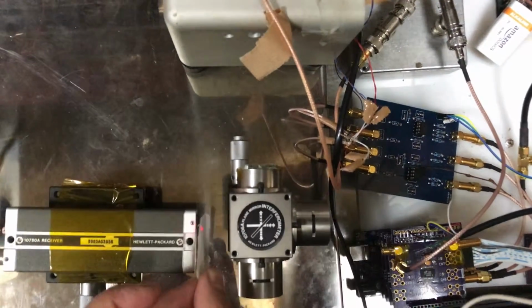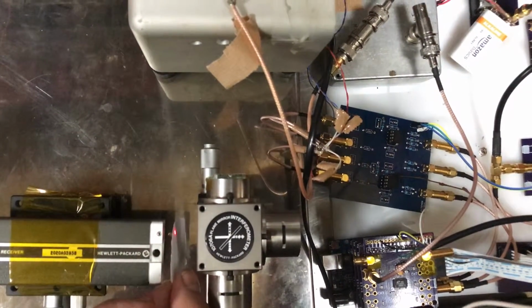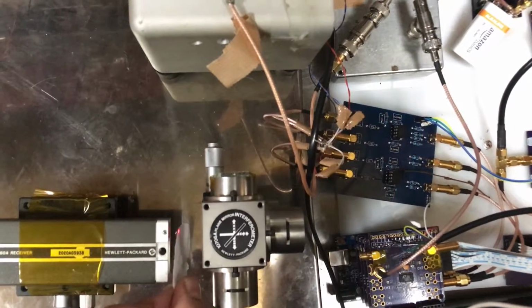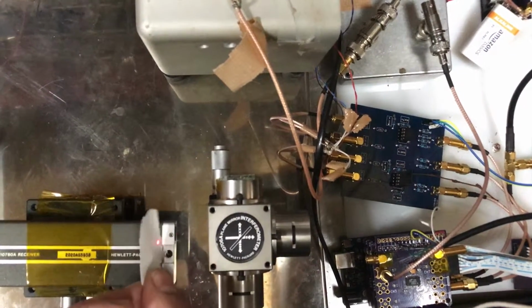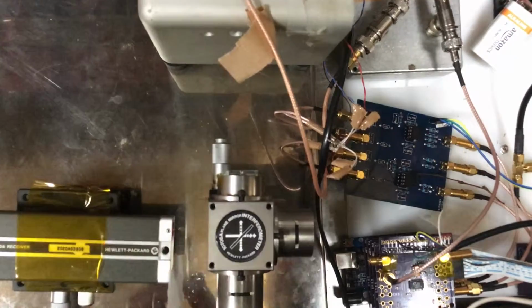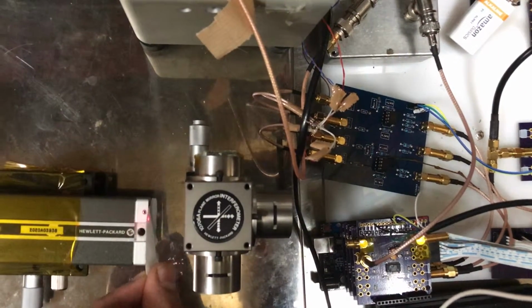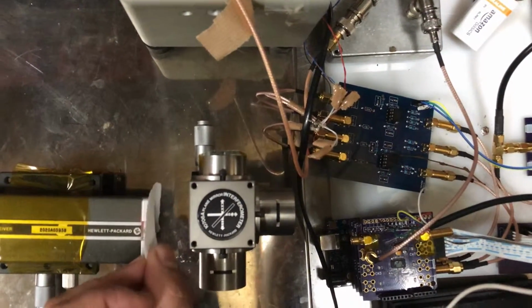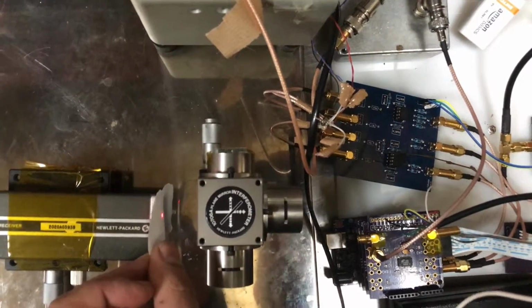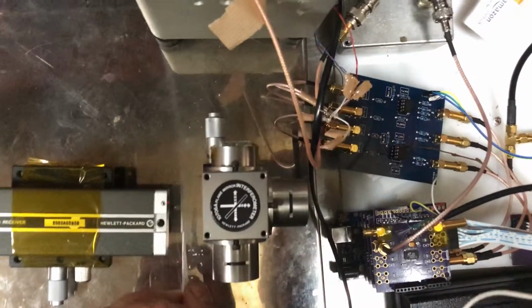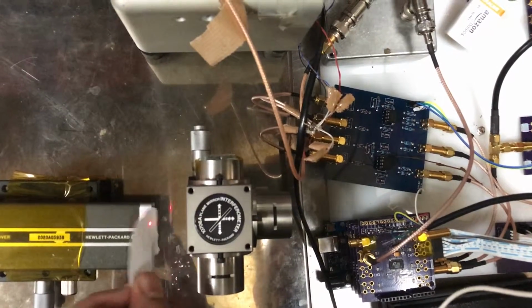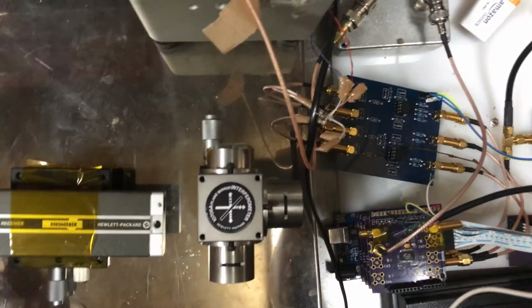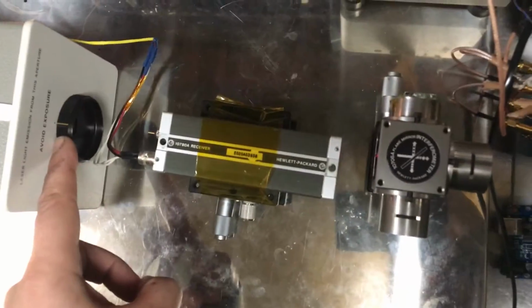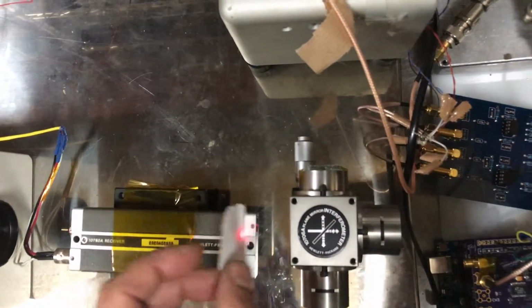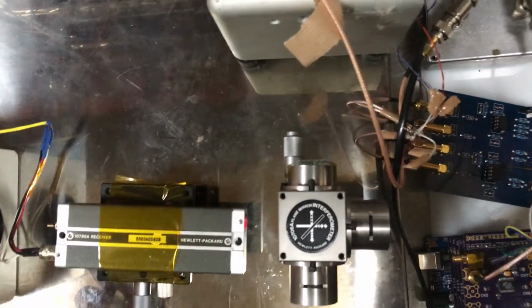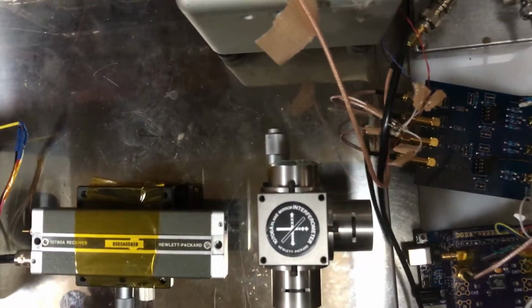So to align it, you get these two beams coming out. This is the incoming beam at the top, and so to align it, you have to come up from the bottom, because if you interrupt this top beam, obviously you don't get anything out anymore. It doesn't go into the interferometer. So there's a setting on the laser to use the full beam or just a little bit of it.